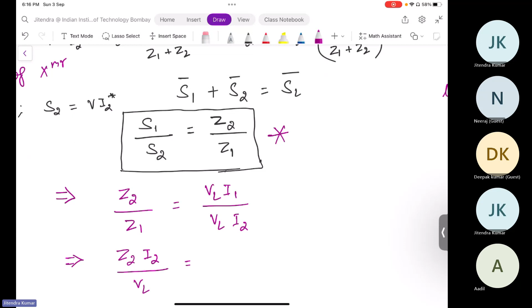So what you can observe from this expression, where we are heading to one very important conclusion: when a transformer is operating directly proportional to its rating, in that case, the per unit impedance of both transformers will be equal. But there is a catch, it will be in their own base.